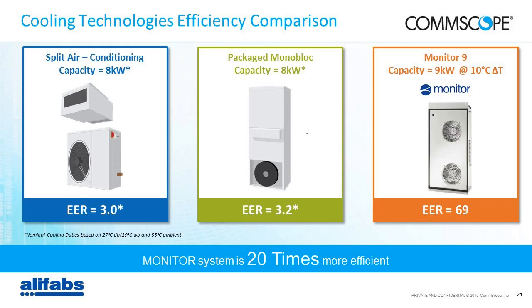Well, split air conditioning, some of them do propose free cooling, some of them do have inverter control, but typically the energy efficiency ratio, the EER, is gravitating around about 3. So that means that it's giving you 3 times in cooling what it's actually using in electricity. So for each kilowatt that it will give you in cooling, it will be burning 300 watts.